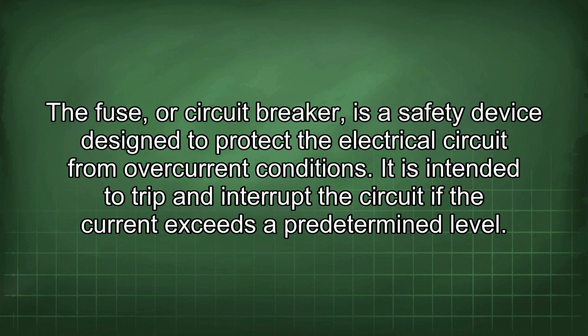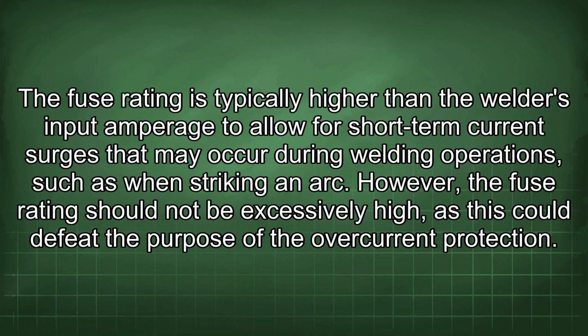The fuse, or circuit breaker, is a safety device designed to protect the electrical circuit from overcurrent conditions. It is intended to trip and interrupt the circuit if the current exceeds a predetermined level. The fuse rating is typically higher than the welder's input amperage to allow for short-term current surges that may occur during welding operations, such as when striking an arc.